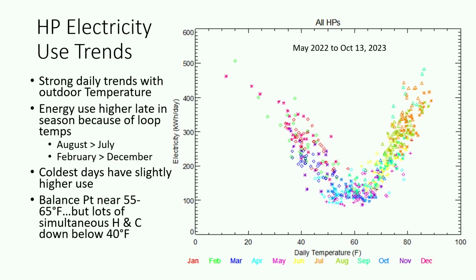Here's heat pump energy use plotted versus the daily average temperature, and each month is a different symbol. Here's what happened on a peak winter day, and here's what happened on a peak summer day. Down here, this mushy middle is my evidence that there was a lot of mixed heating and cooling. Sometimes buildings have a heating balance point and a cooling balance point. Here it was all muddled together. I think that's what you would expect in multifamily, where people are doing different things in their spaces. So you see this mix of behavior.